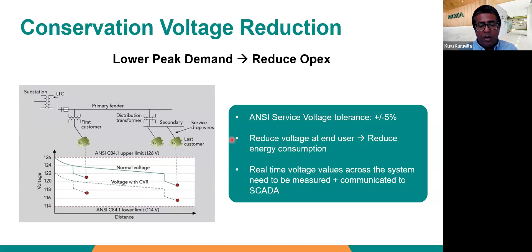But this requires very tight management of the voltage, because if you reduce the voltage too much, you could run into regulatory issues, as an example violating ANSI standards. So you need a very good idea of what the voltage at the last node is, which means you need to be able to sense it, and send that information back into, for example, a SCADA system.